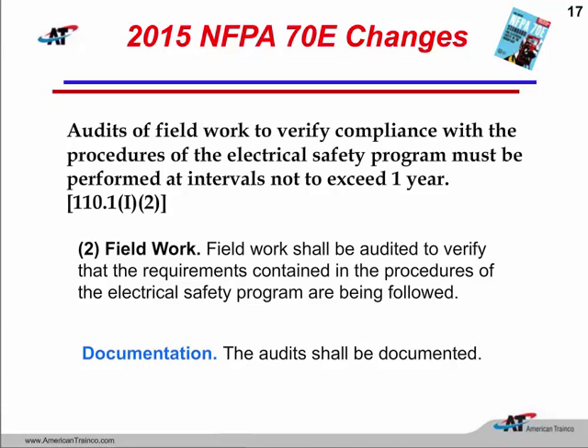So we're going to have to go out in the field. We're going to have to audit our qualified electrical worker to make sure that that worker is following all the safe procedures that we have in our safety program. We're going to have to make sure that the proper PPE is on, that we're doing lockout, tagout the way we should be, that we are doing our visual verification to establish that electrically safe work condition. So probably another form will have to be generated here so that we can perform this audit.